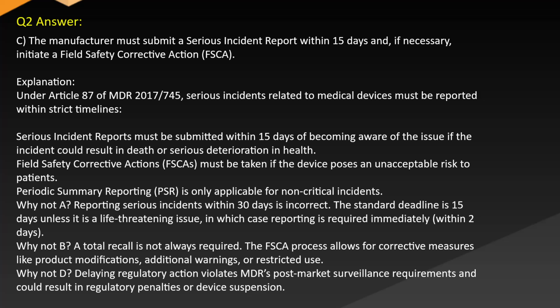Answer. C. The manufacturer must submit a serious incident report within 15 days and, if necessary, initiate a field safety corrective action (FSCA). Explanation. Under Article 87 of MDR 2017-745, serious incidents related to medical devices must be reported within strict timelines. Serious incident reports must be submitted within 15 days of becoming aware of the issue, if the incident could result in death or serious deterioration in health. Field safety corrective actions (FSCAs) must be taken if the device poses an unacceptable risk to patients. Periodic summary reporting (PSR) is only applicable for non-critical incidents.